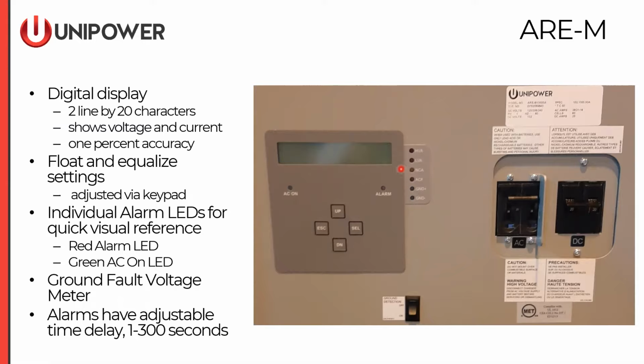Meter display is 1% accuracy. Float and equalize settings, as well as all user assignable parameters, are adjusted via front keypad and submenu structure that's displayed on the 2-line display. All chargers, 100%, are equipped with individual alarm LEDs for a quick visual reference to any operators that are on site. You have a red alarm LED that's normally not on, just below the display.